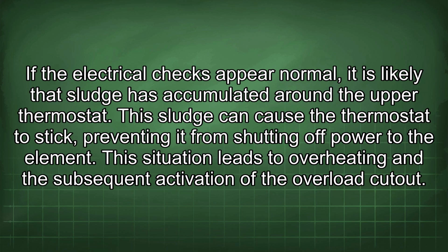If the electrical checks appear normal, it is likely that sludge has accumulated around the upper thermostat. This sludge can cause the thermostat to stick, preventing it from shutting off power to the element. This situation leads to overheating and the subsequent activation of the overload cutout.